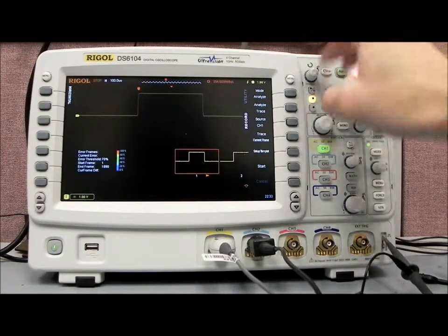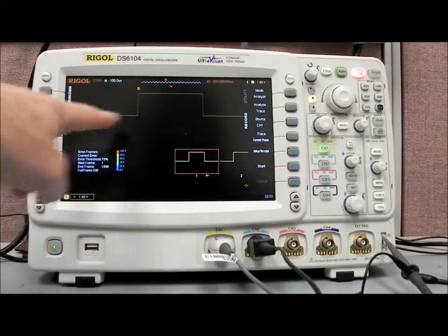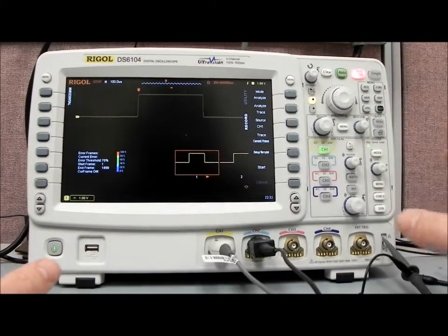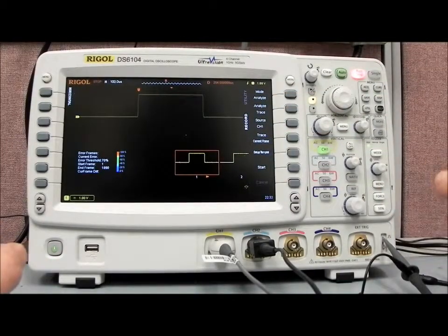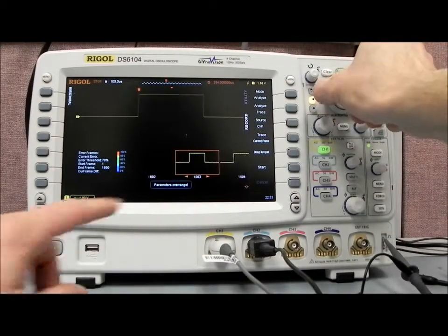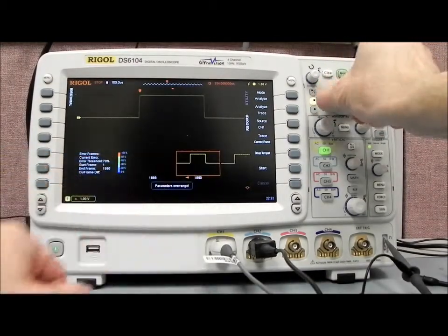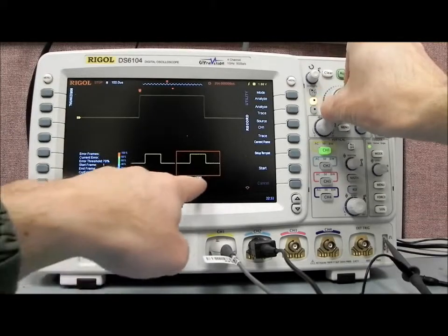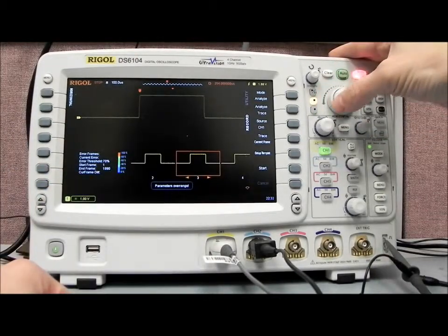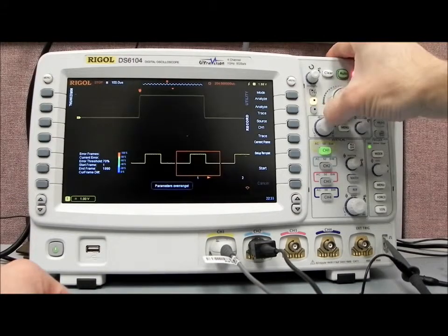And in Analysis, you'll see now we have a split screen. On the top screen, we have a picture of the first frame of a waveform, or the first waveform that we've collected in memory. And we can select any number of those by using either the outer ultravision knob, which is going to give us a fast forward effect. You can see that we're zipping along now, we're at 1,890 frames, or we can do one at a time using the inner knob, where we go 5, 6, 7, 8, and back again.